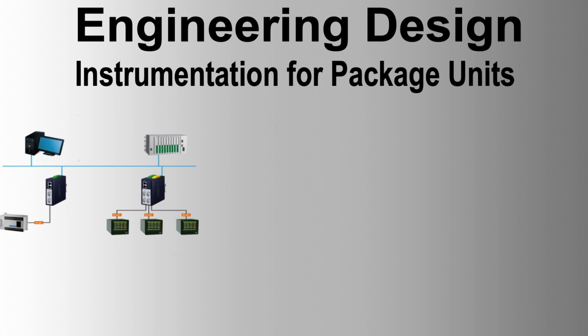1. Instrumentation loop and block diagrams for the control and operation of the equipment, showing all instrumentation together with connections required, using the principal's instrument symbols and tag numbering system. 2. Functional logic diagrams and function descriptions for startup, sequence control, IPF, and emergency shutdown procedures. 3. A list of all instruments giving the make and type, operating data, and length of thermowells. 4. Typical process hookup drawings.